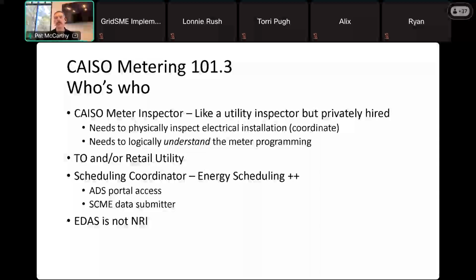So there's a program inspection, there's a physical inspection, and all of that should take place well before your point-to-point test, as Kelsey mentioned. We'll get more into point-to-points in a minute, but I really want to hammer on this role of the CAISO inspector. As far as I can tell - and I teach utility guys at a metering school up in Seattle - what we do here is much more in depth than what most other utilities do, because the dollar amounts and the energy volumes are much higher. It's just much more important.